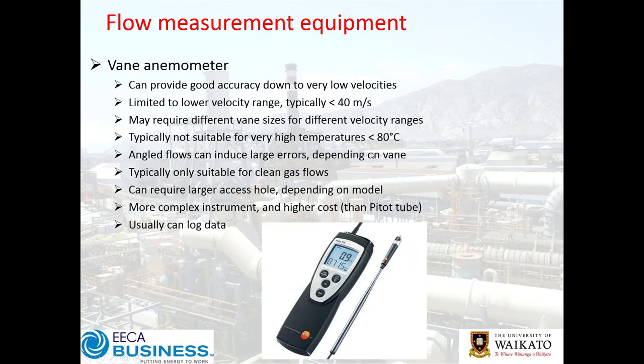Hot wires typically have built-in temperature and often humidity measurement options as well. A vane anemometer — essentially a little propeller — is generally in the low velocity range and can be good at very low velocities. Multiple vanes are often needed, and they're fairly cost effective. There are some questions about how well they perform with dirtier flows, though provided you keep the vane clean it shouldn't be too much of a problem.